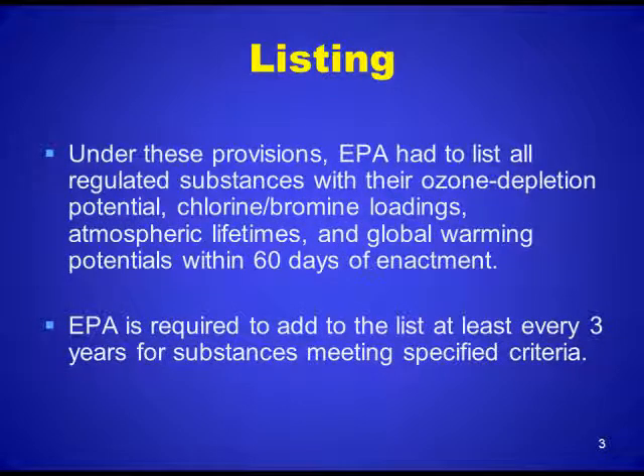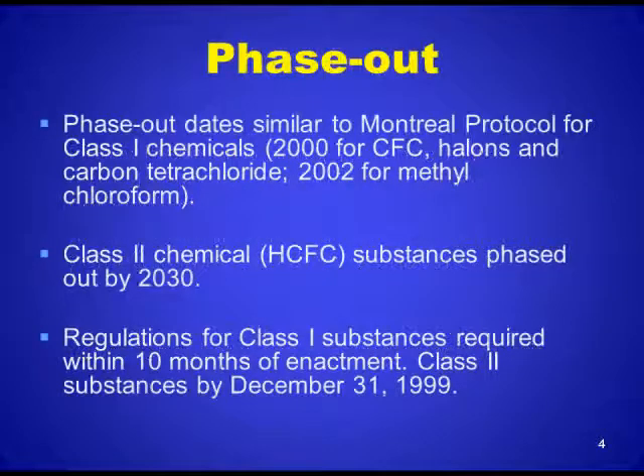Under these provisions, EPA had to list all regulated substances with their ozone depletion potential, chlorine/bromine loadings, atmospheric lifetimes, and global warming potentials within 60 days of enactment of the 1990 Amendments. EPA was required to add to the list at least every three years for substances meeting specified criteria. Phase-out dates similar to the Montreal Protocol for Class I chemicals: 2000 for CFCs and halons, and 2002 for methyl chloroform, with carbon tetrachloride also included.